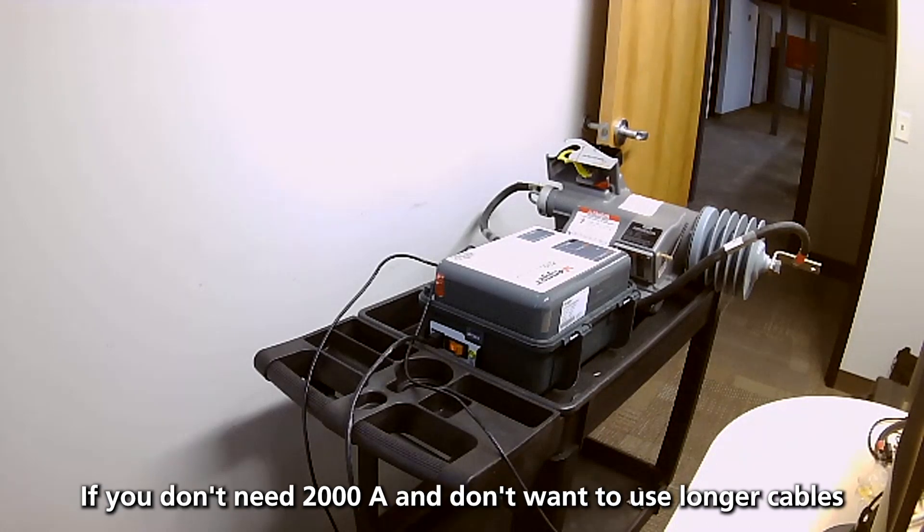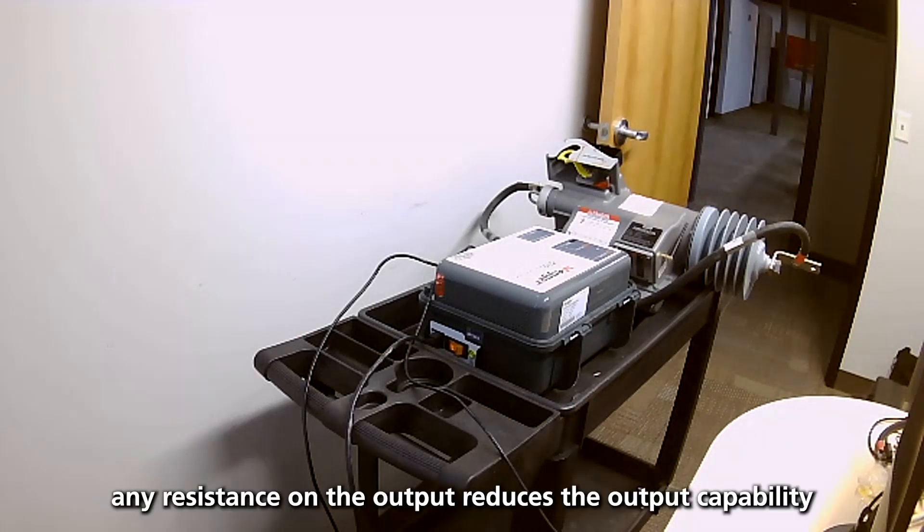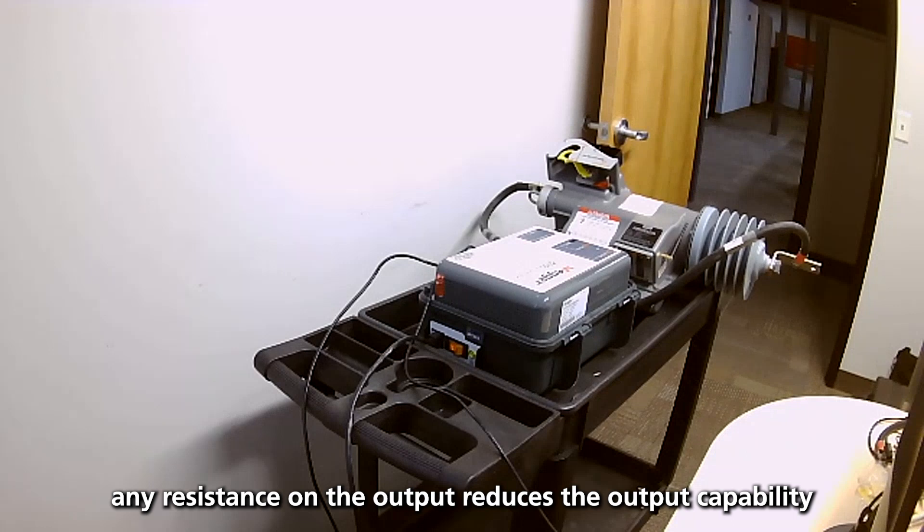If you don't need 2000 A and don't want to use longer cables, you can, but you do need good bolted connections. Any resistance on the output reduces the capability.